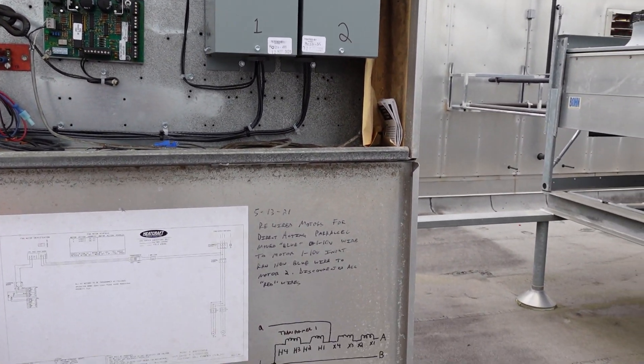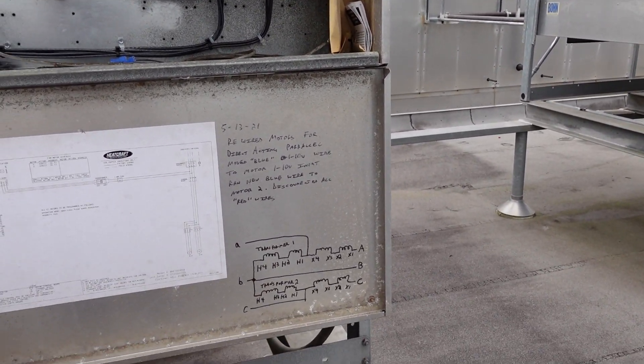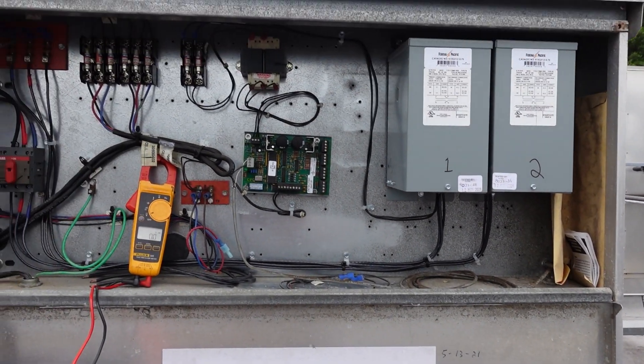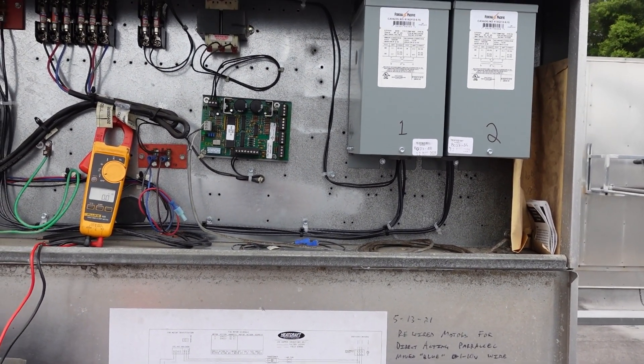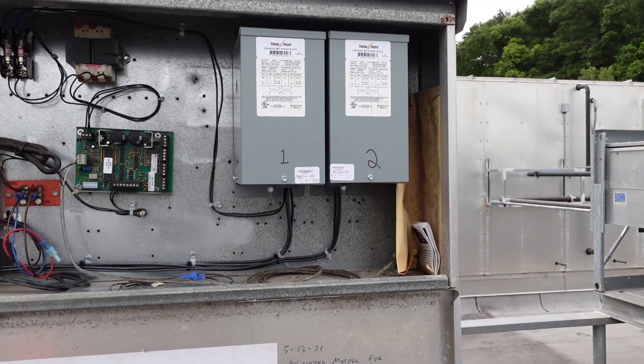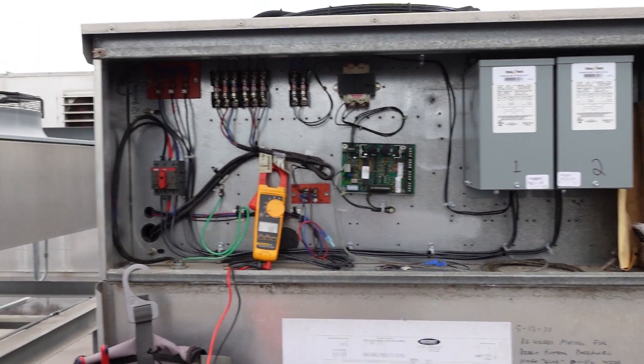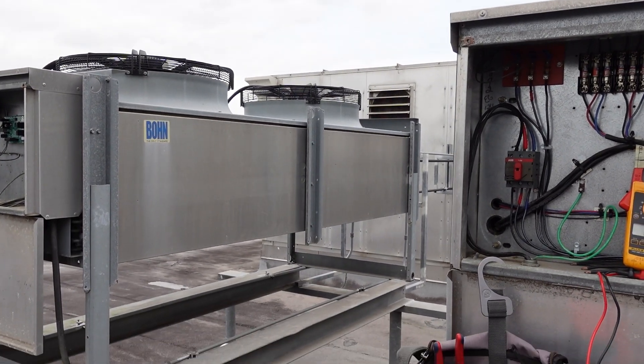You've seen these units before, maybe not this specific one, where we rewired the condenser fans so if one fails it doesn't necessarily take all the rest out. But we're trying to eliminate fan failures altogether, especially on these two fan condensers.